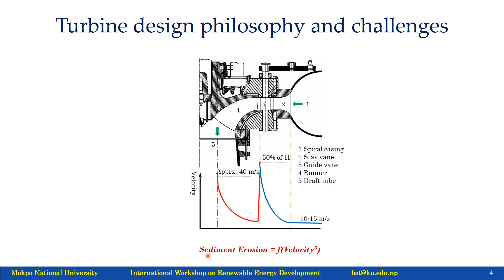This is the Francis turbine. In fact, the biggest Francis turbine installed in Nepal, 48 megawatts. And at the outlet, you can see almost 30% of the runner blades is washed off due to the sediments. Several methods have been tried. You can see some remains of HVOF coating, which is a very hard coating. Even that doesn't work well, and this is due to the high velocity peaks in the standard Francis turbine. This is the biggest Francis turbine installed in Nepal, installed in India actually.